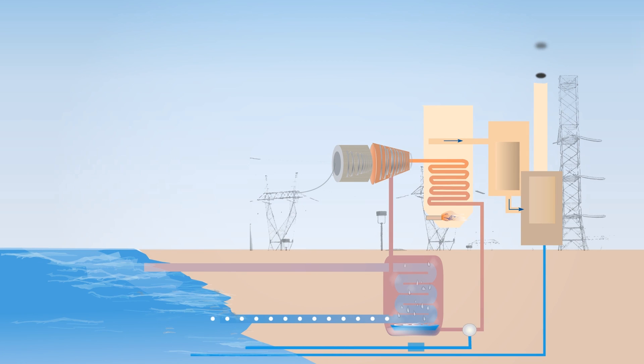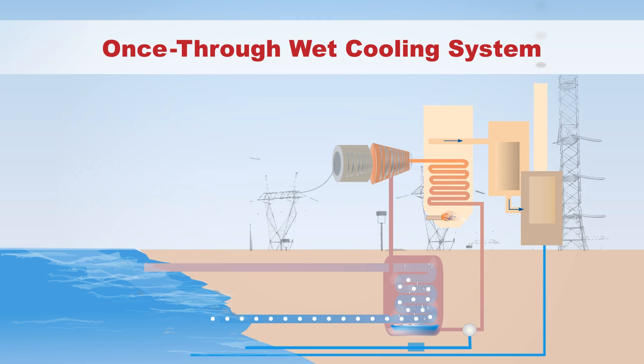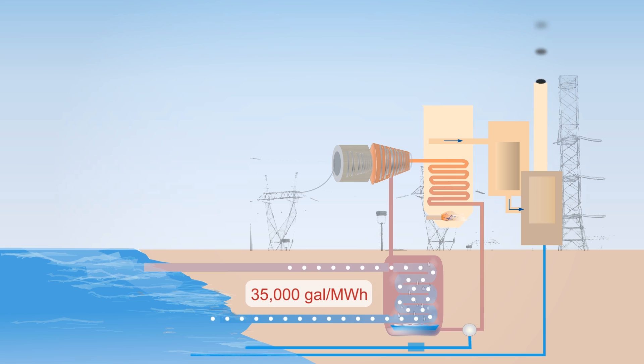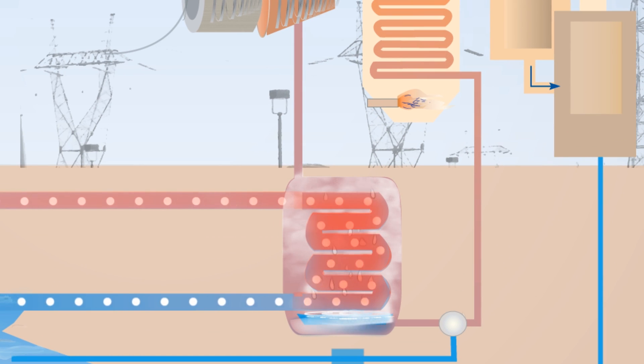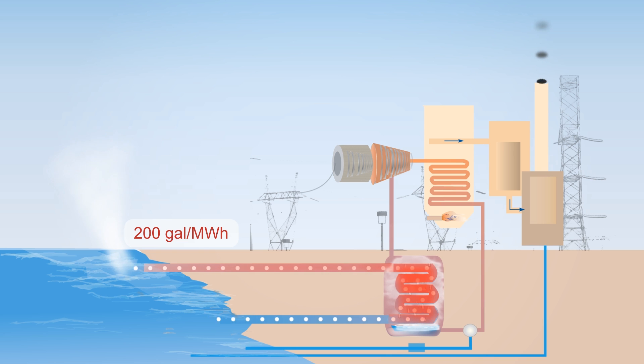A typical coal-fired power plant with a once-through wet cooling system withdraws about 35,000 gallons per megawatt-hour of electricity generated, but returns most of it to the source. After the water is withdrawn from the river, lake, ocean, or reservoir, it is used to condense steam in the power plant. In the condenser, it absorbs heat from the steam and is then returned to the source, with 200 gallons lost to evaporation per megawatt-hour produced.